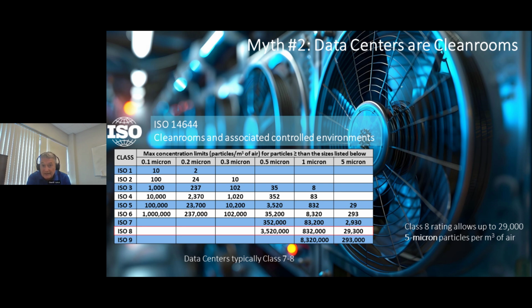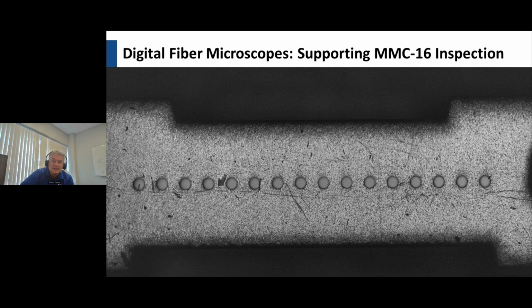There is actually an ISO rating for different environments. The actual rating for a typical data center is in what they call the category 7 or 8 range, which in category 8 allows up to 29,000 five-micron particles floating around in a cubic meter of air. If you think about it, just one of those, if it lands on the core of a fiber, could be enough to contaminate it and cause a network outage. So again, the importance of good inspection and cleaning practice is critical for these data centers.